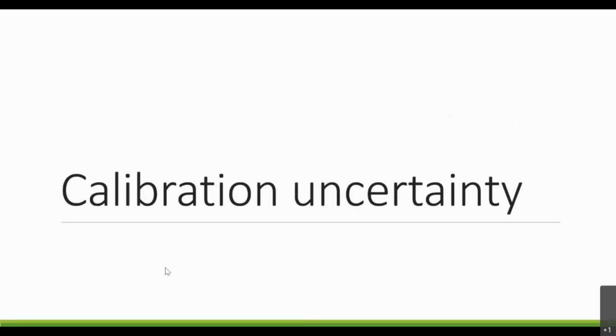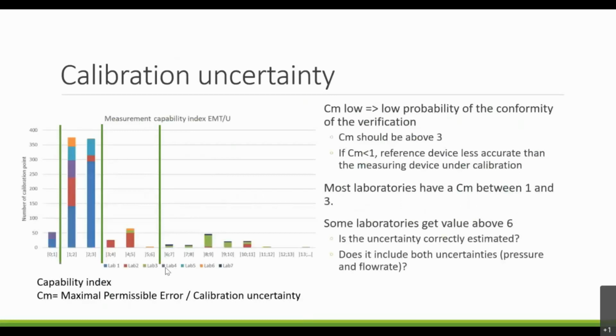Now let's come to the last part of this presentation, about calibration uncertainty. We have plotted here the capability index of the laboratories that are performing the calibration. The capability index is the ratio between the maximum permissible error and the calibration uncertainty. Basically, when you are calibrating a device, you assume that the uncertainty of the laboratory is much smaller than the maximum permissible error of the device you are calibrating. If you want to reach a maximum of 5% of error, you assume that the laboratory has an uncertainty below, let's say, 2%. And usually what we say is that this ratio shall be above 3. So that means that the maximum permissible error is 3 times higher than the calibration uncertainty.